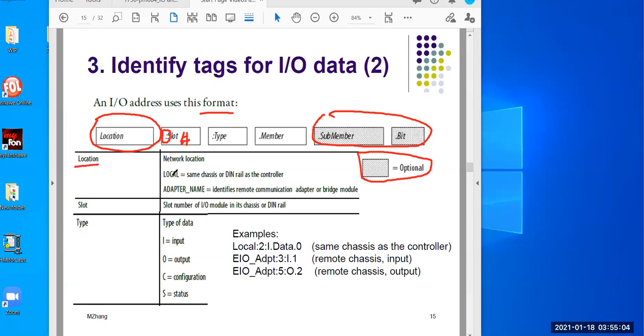With location, you can have two types. If you have a local chassis — the same chassis and same backplane as the controller — then it's local. Or you can have remote I/O, meaning the module is not installed on the same chassis or backplane as the PLC controller; it's somewhere else. The most popular option is Ethernet I/O, where the I/O module is connected to the PLC through Ethernet rather than locally.